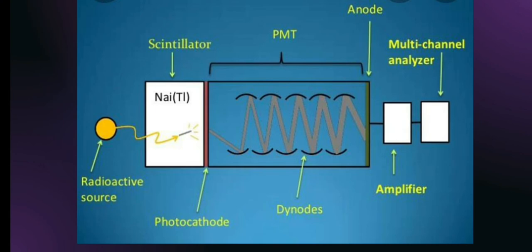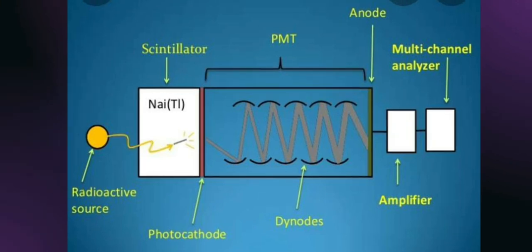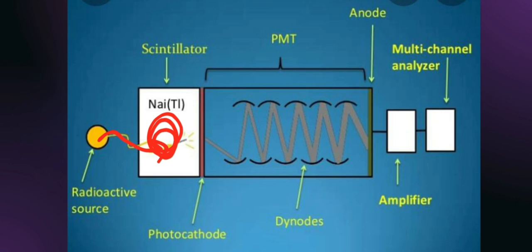When the radioactive material emits gamma radiation, this gamma radiation falls on the scintillator. The gamma radiation releases electrons from the atoms of the scintillator, and this electron excites all the atoms along its path. When these excited atoms return to their ground state, they release a flash of light. These flashes of light cause the photocathode to emit electrons.